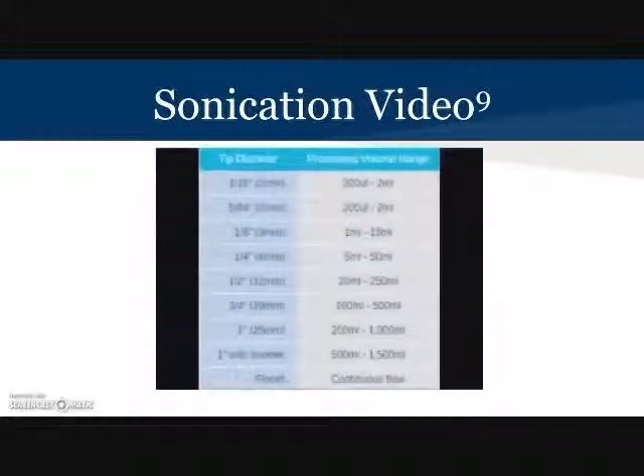There are different sized probe tips based on particular sonication processes, so it's important to select the proper size. Looking at the chart, you may see that each probe has a recommended sample volume range. Sample volume size and shape is also a factor when considering what tip to use. Using the proper size probe will not only reduce the processing time, but also increase the lifespan of the probe.